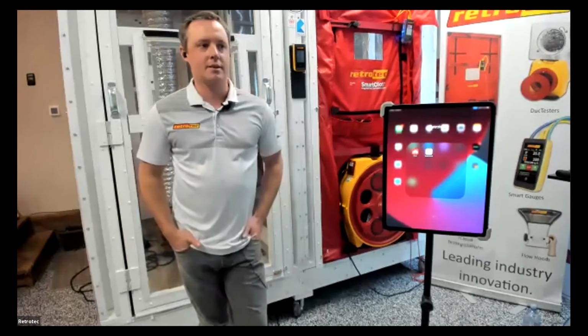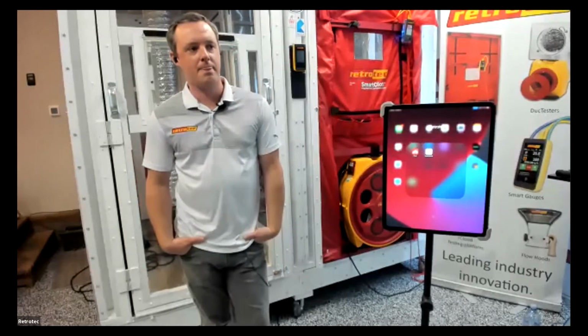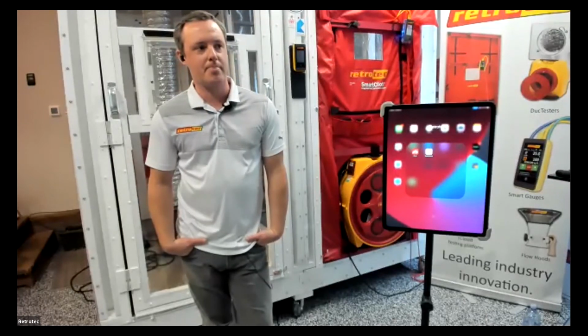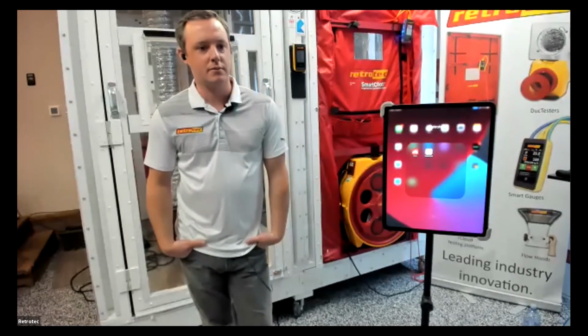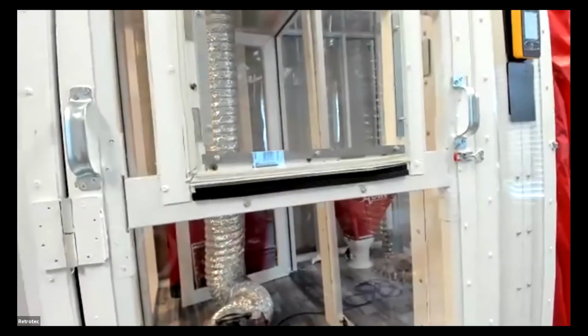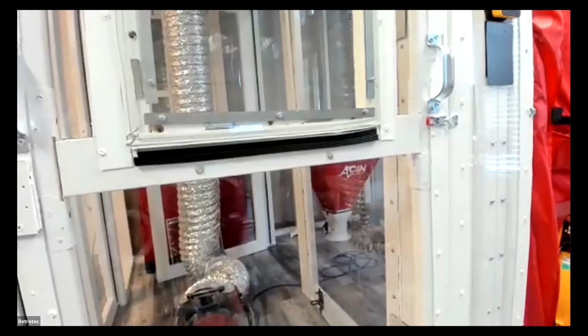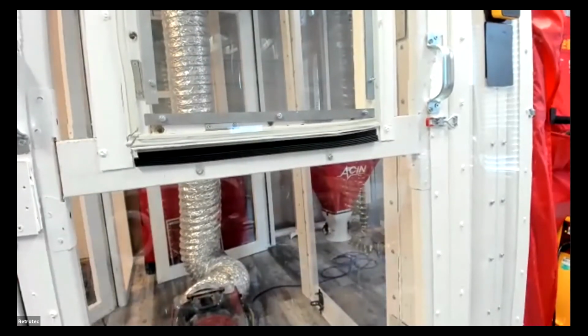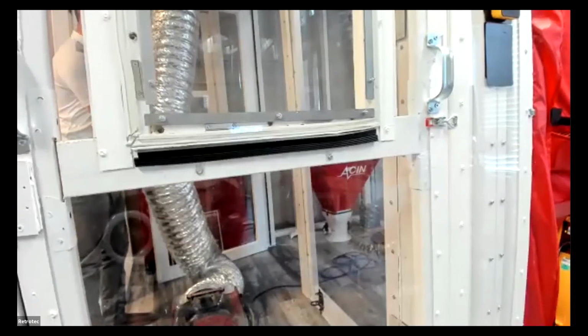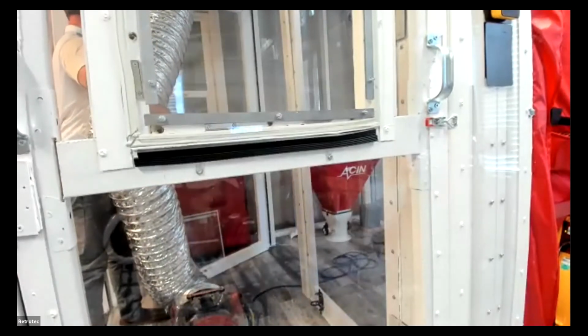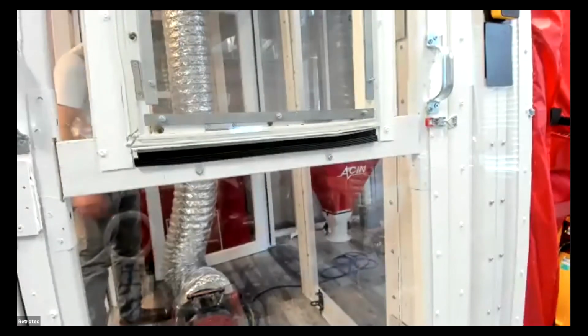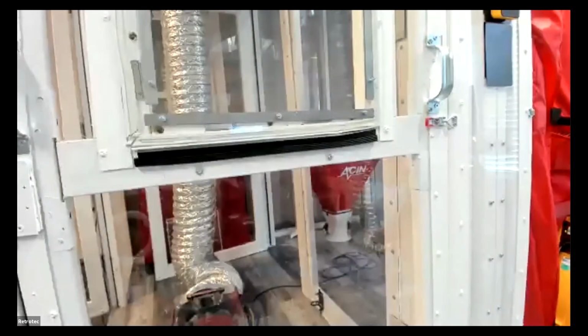And someone was asking if your test enclosure that you built here, if the two zones are connected, since you're running the fan on the right side and the duct tester was on the left. There is a connection between those two zones. Yeah, so let's see if I can grab the camera here. See if I can get you to look in there. What you see behind that flex is, well, I've got two double doors in here, so I can have this set up to be like 2 apartment units if we wanted to do guarded testing, but I've got one of these doors open. So the entire space is connected. They're not separated from each other. One of those doors is wide open.